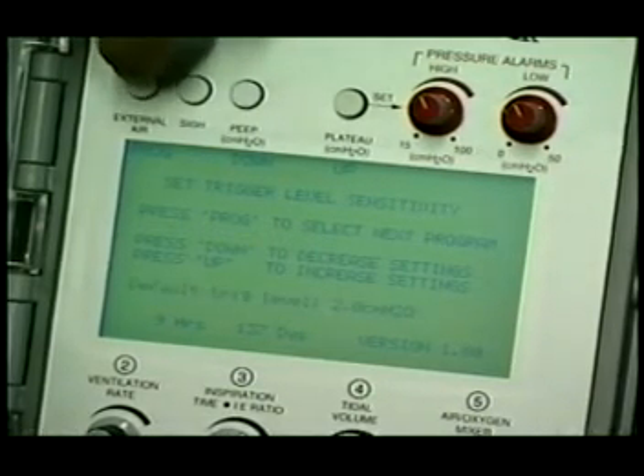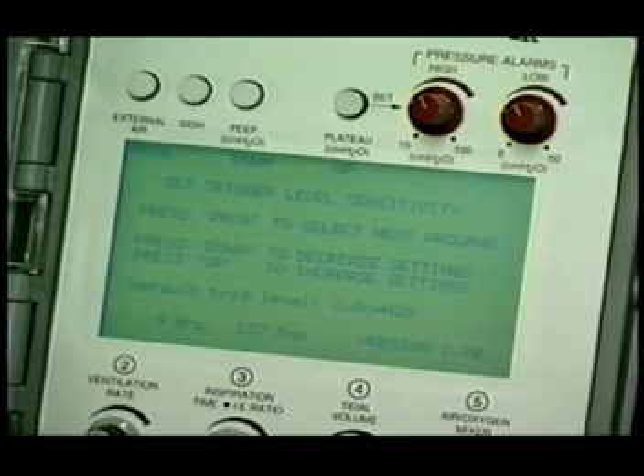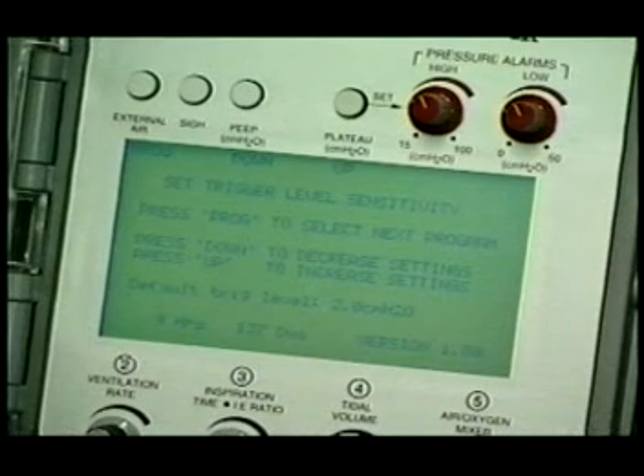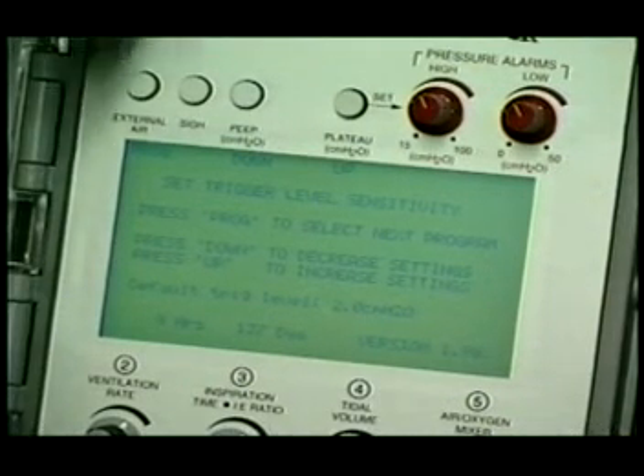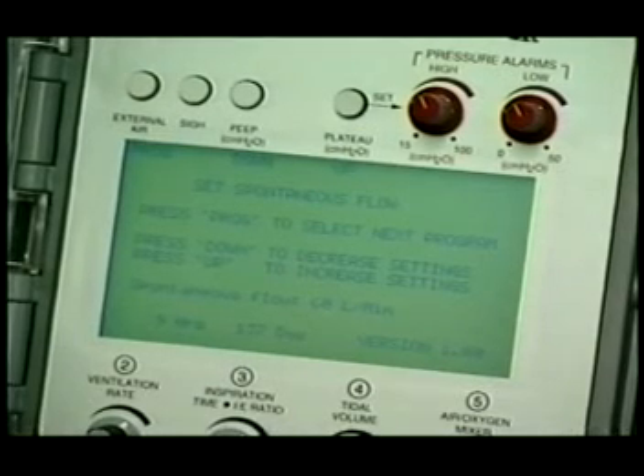The next menu allows us to temporarily change trigger level sensitivity, which controls the inspiratory work of breathing set point for patient-triggered breaths. This temporary change is for the current operating sequence only. When power is turned off, the normal default value will be restored the next time power is turned on. We can also lower the spontaneous flow for use in SIMV and CPAP on smaller patients. It too is a temporary setting for the current operating sequence and reverts to its default value when power is turned off and then on.